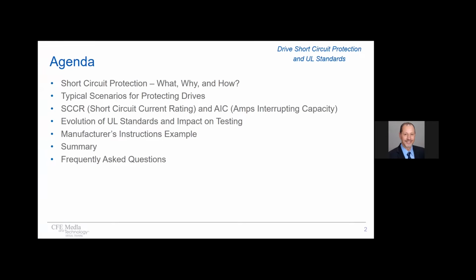So looking at the flow of topics for today, we're going to talk about short circuit protection, the what, why, and how, typical scenarios for protecting drives, and these two terms that often get confused, which are short circuit current rating and amps interrupting capacity. We'll talk about the evolution of the UL standards and the impact on testing for drives. We'll look at an example of manufacturer's instructions to make sure that protective devices are properly applied. And we'll wrap it up with a summary followed by some questions.